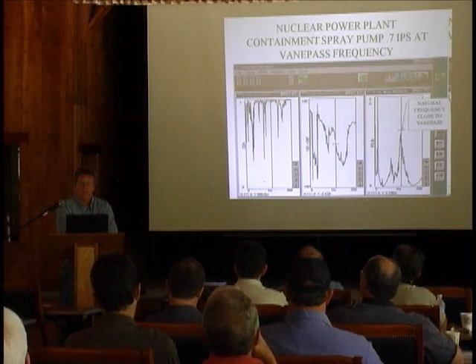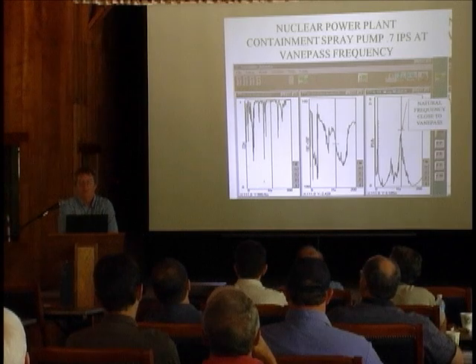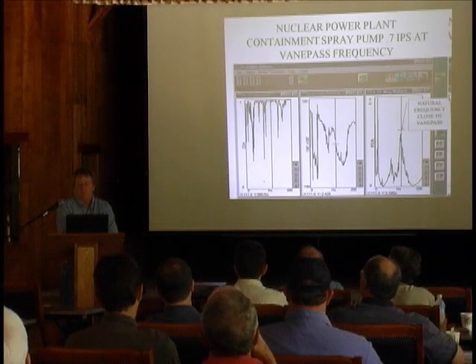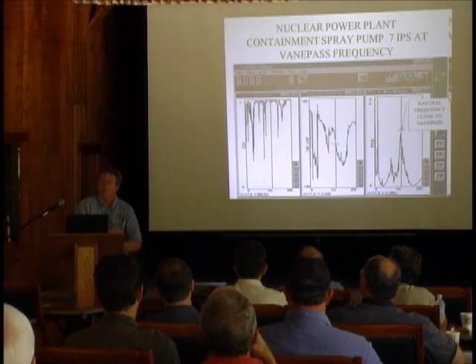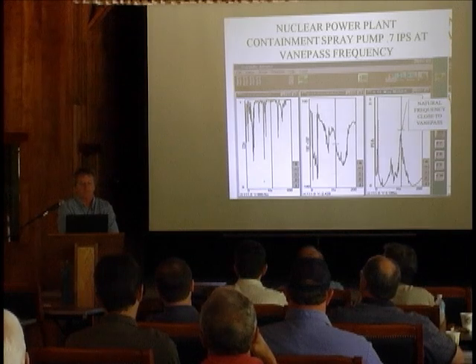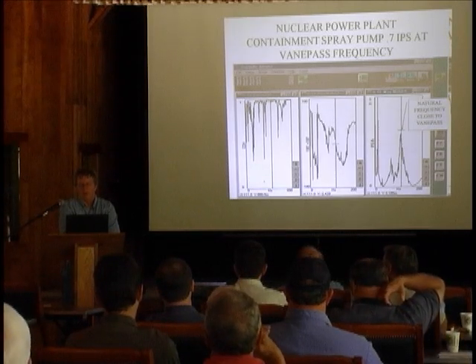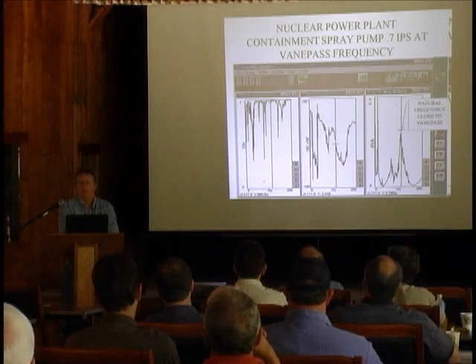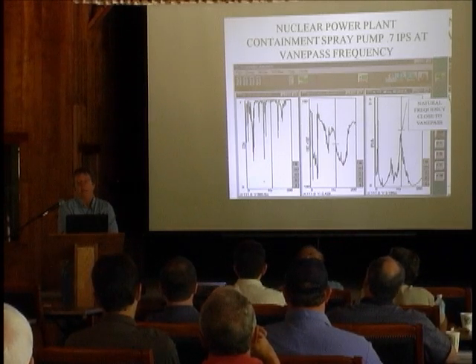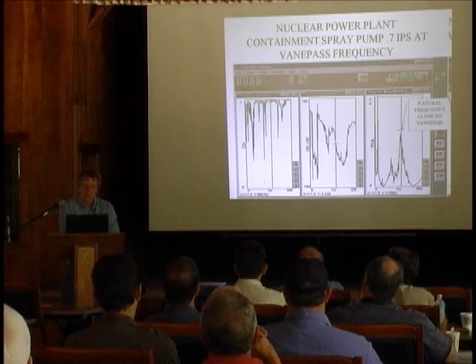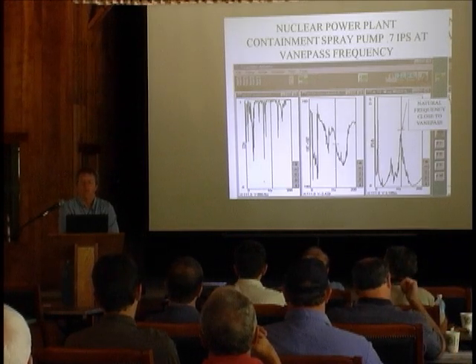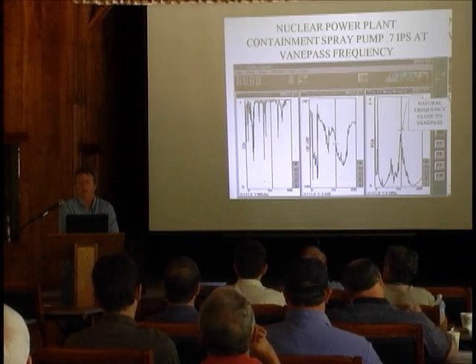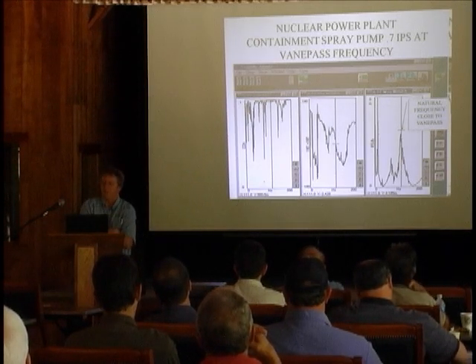But once you've done that, then you have to spray that steam to condense it, and you spray it with borated water. And so these containment spray pumps, they don't run very often. Again, they just test them once every month. So I had noted there had been a problem on this for years. The vane pass was just about to the limit of what the ASME and the NRC would allow. And finally, it got right to the limit, which was 0.7 in this case.